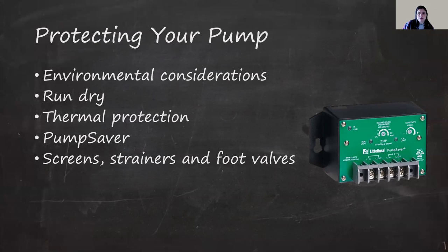For example, some pumps have built-in thermal protection, which shut off the pump if the motor becomes too hot. Many of the intermittent use pumps do not have this feature, as they presume you will use it correctly, only for a few minutes at a time, and then allow it to cool. There's no built-in thermal protection, consider wiring an inline thermal switch.